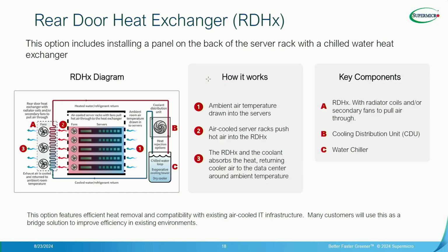A couple other things: rear door heat exchangers. Think of this as a CRAC unit on the back of the rack, simple as that. You still have air-cooled equipment in the rack, it's still using cold air, blowing it over, exiting hot air. But what you have is essentially a little cooling coil right at the back of your rack.